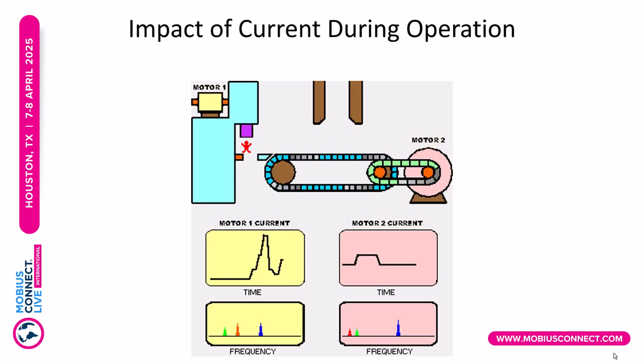So if I have equipment running, every time I have a variation in the driven equipment or power supply or whatever else, it always passes through that field and has an impact on that field, and I measure that back as a relationship primarily in current. But voltage, if it's nice sinusoidal, perfect, no issues, no harmonics, then anything riding in my current is very, very definitely going to be whatever defect I'm looking for.